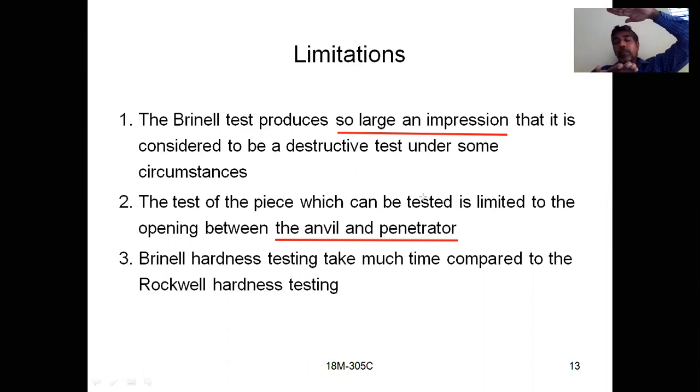What is the gap between your anvil and the penetrator? Only that much size can be accommodated. Beyond that, we are unable to. So that is the second limitation. Size is a limitation, because we can only provide the gap between your indenter and the anvil.